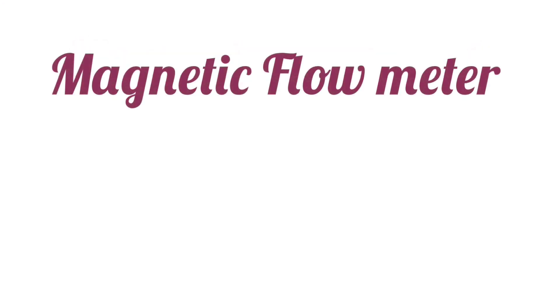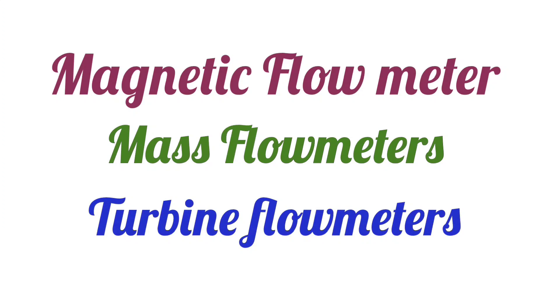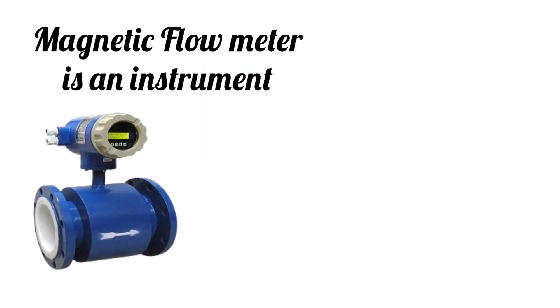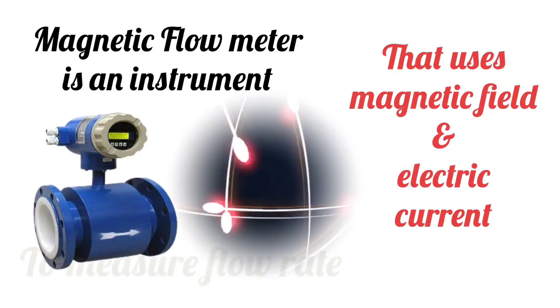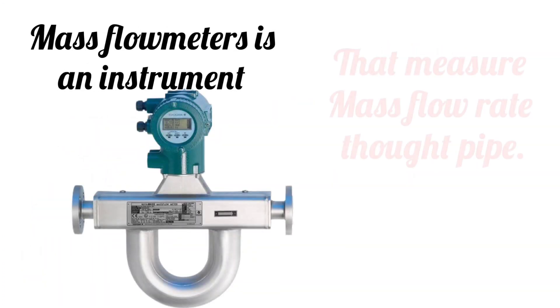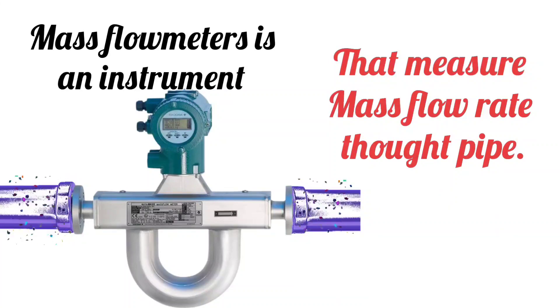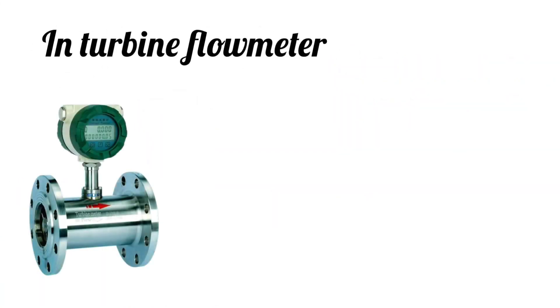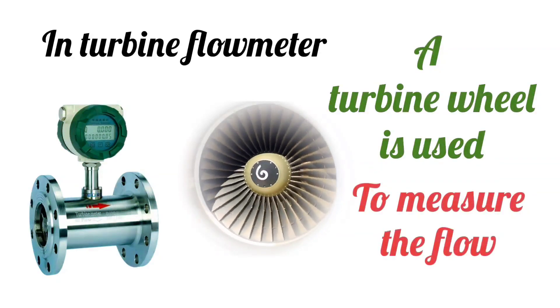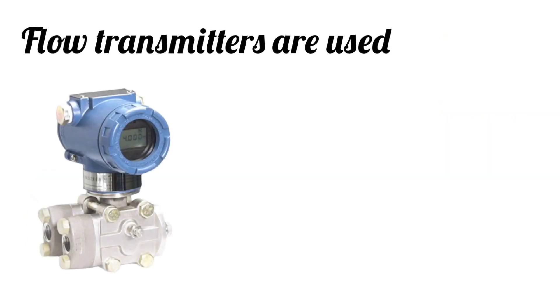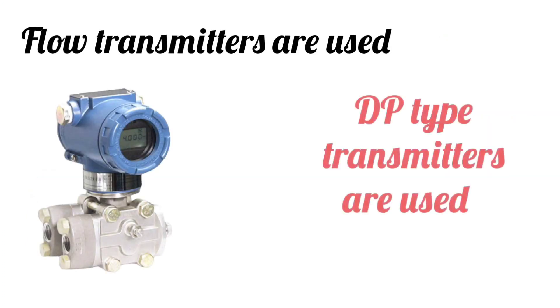Flow meters are used, such as magnetic flow meters, mass flow meters, and turbine flow meters. A magnetic flow meter measures flow rate using a combination of magnetic field and electric current. A mass flow meter measures the mass flow through the pipe. In a turbine flow meter, a turbine wheel is used to measure the flow. In addition to these, flow transmitters are used — specifically, DP type transmitters used with an orifice plate.